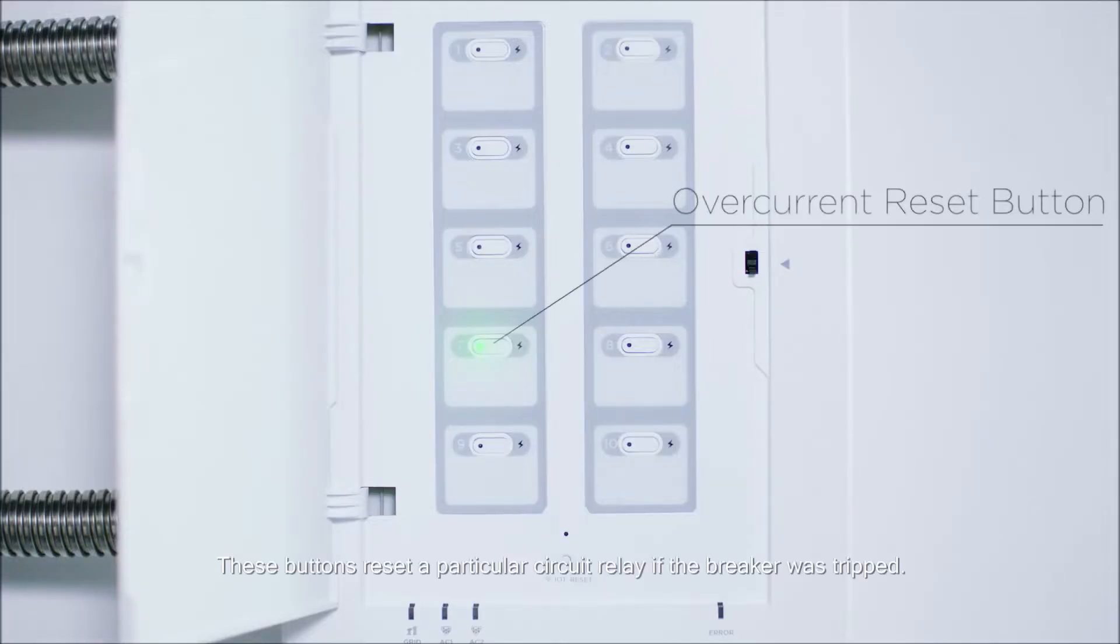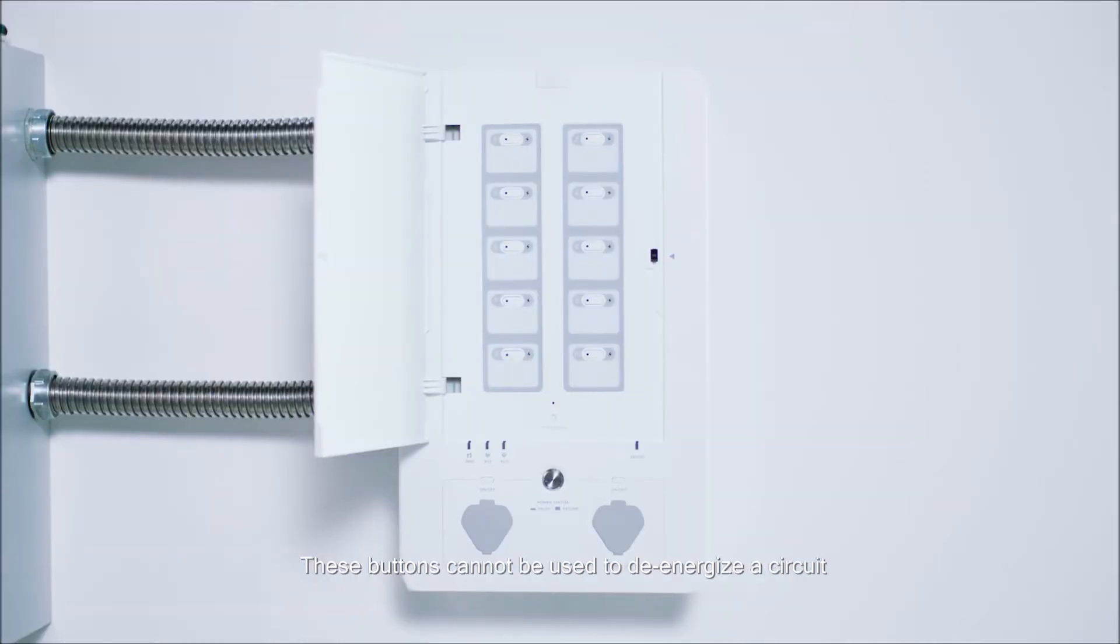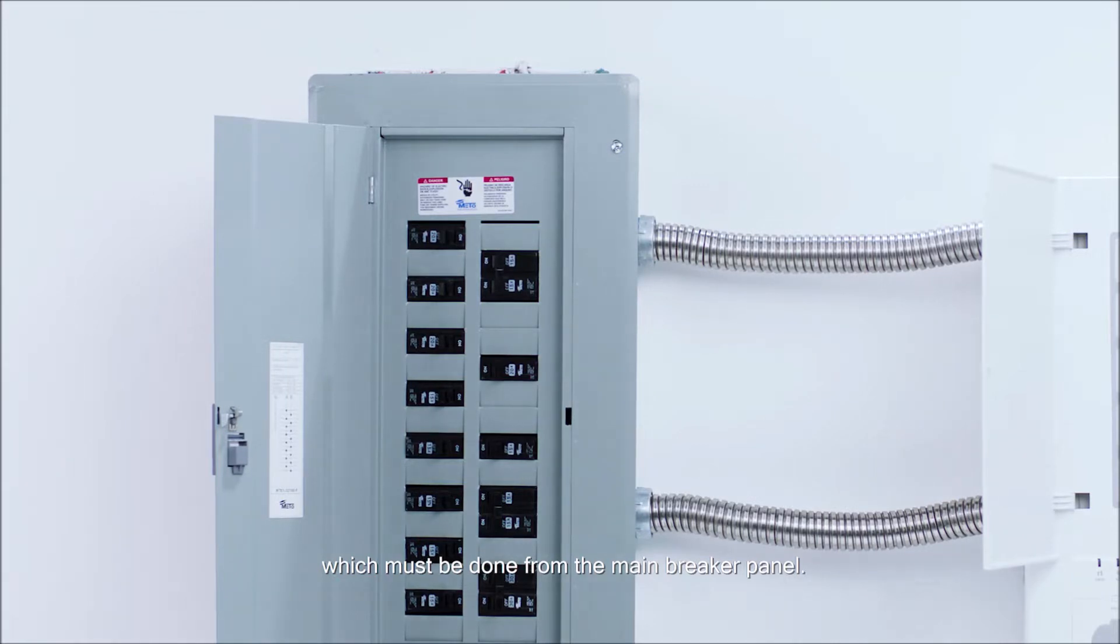These buttons reset a particular circuit relay if the breaker was tripped. A red indicator light means that there has been a fault in that circuit. These buttons cannot be used to de-energize a circuit, which must be done from the main breaker panel.